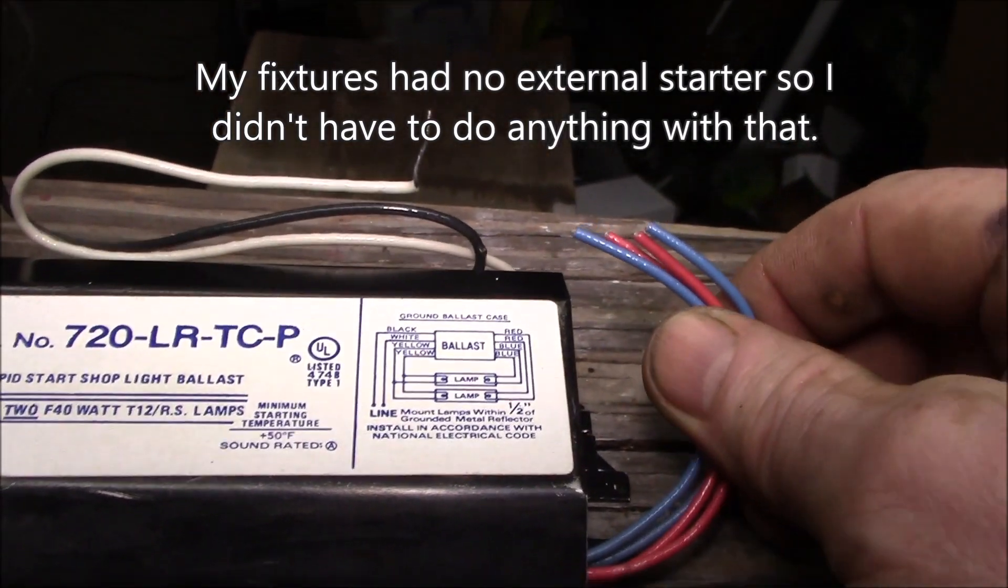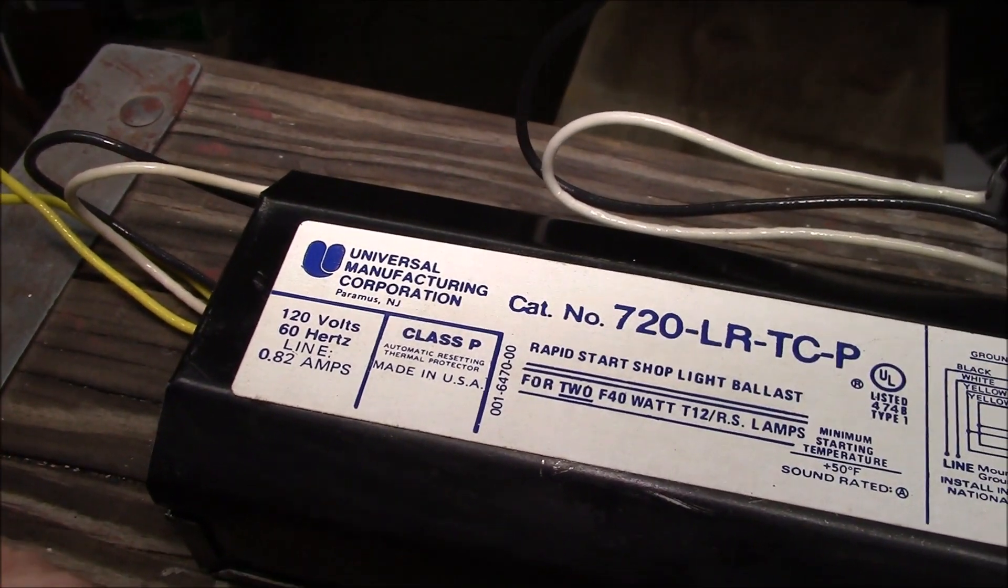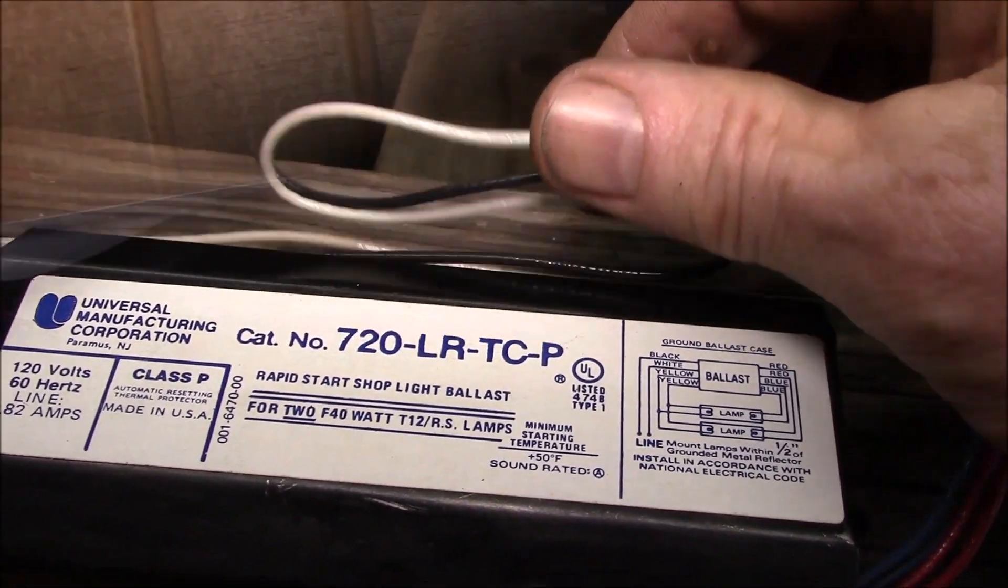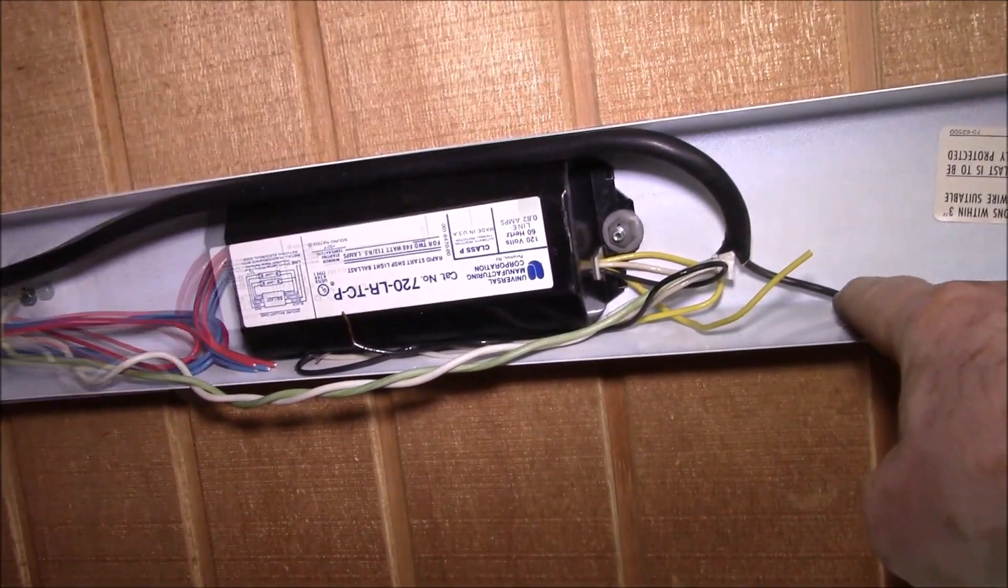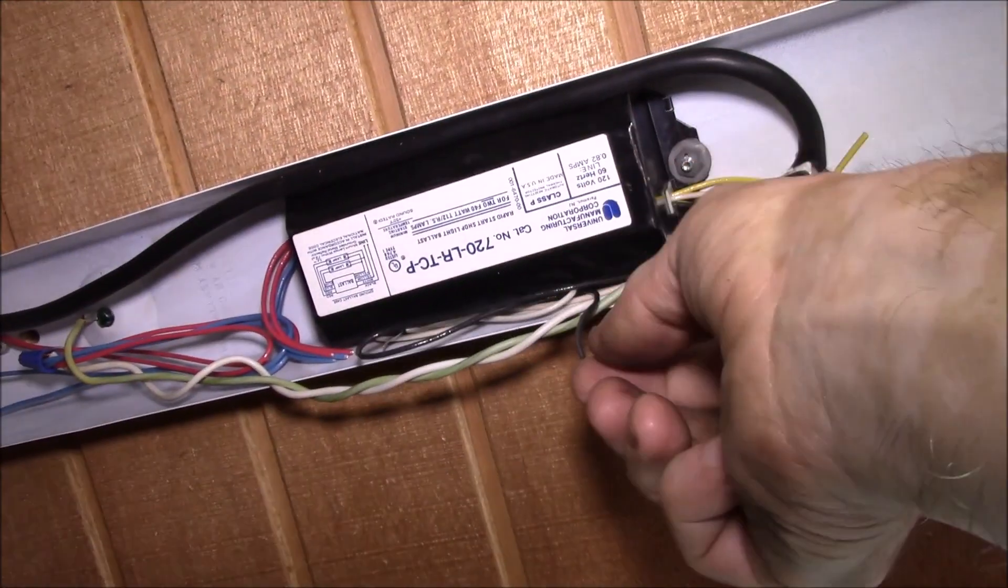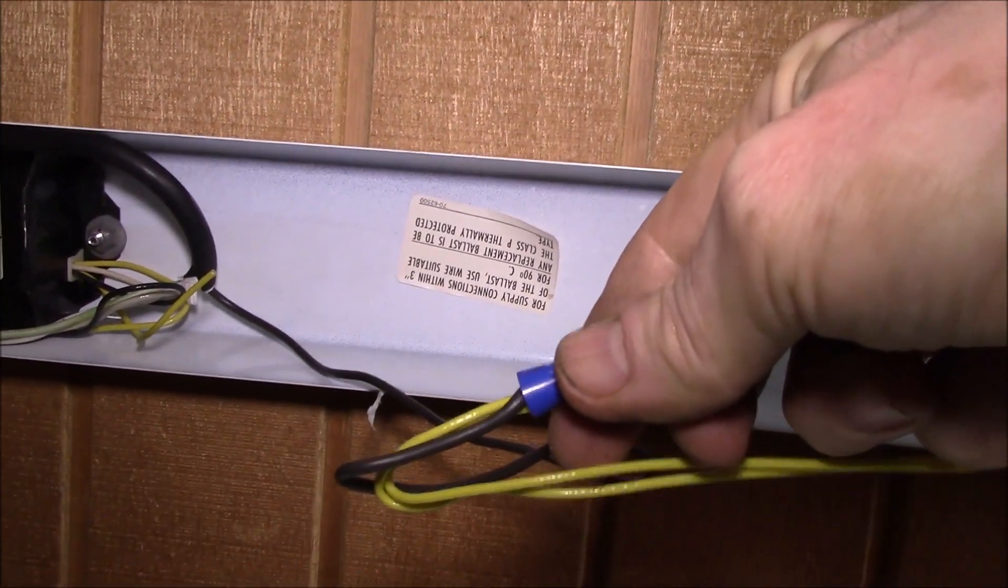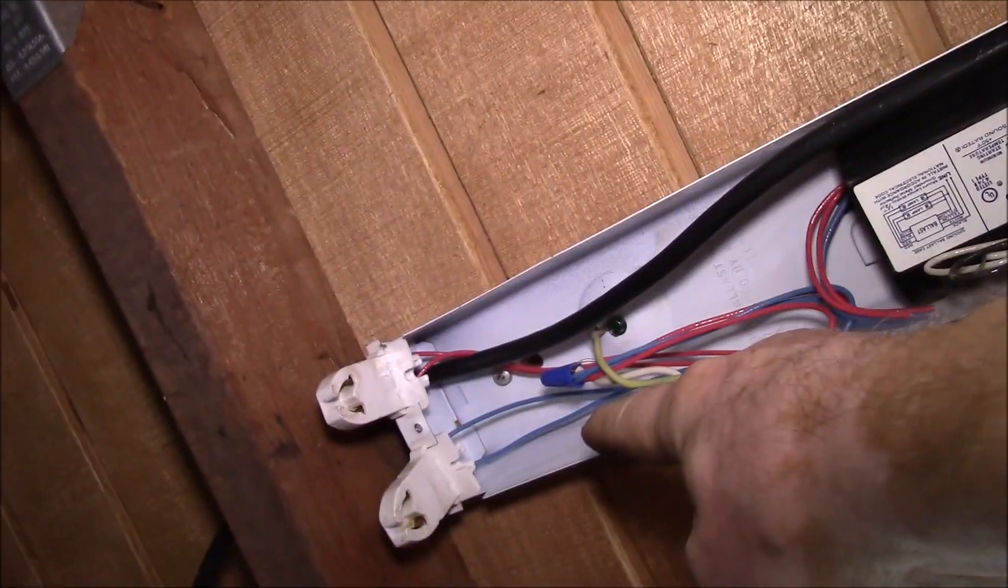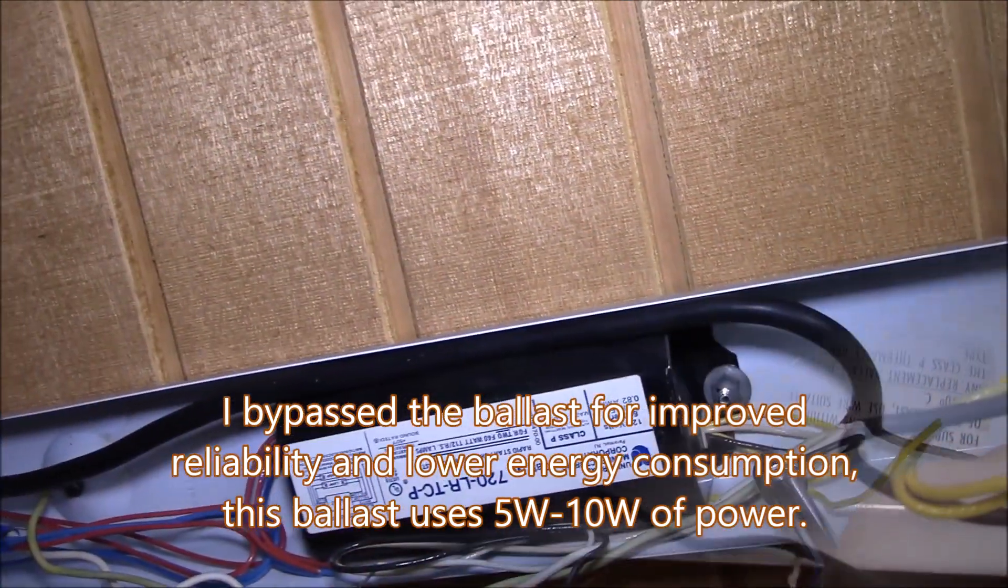Yeah, so there should be probably two or four wires going to one end of the fixture and two or four wires going to the other end of the fixture, and then two more wires hooked to the incoming power. So originally the incoming hot went to this wire that went into the ballast. So I just took the wire nut off that wire and put it onto these wires. And then likewise there was the original neutral that went to the ballast. I disconnected that and connected it over there. And the ballast is just sitting here, it's not doing anything.